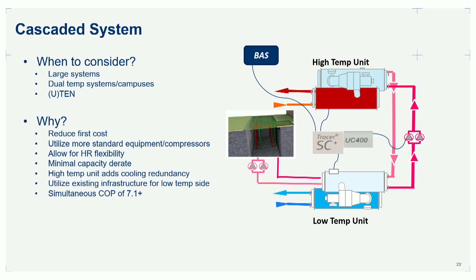Last but not least, I just have an example here to show this in practice, so you can believe me when I say that you can actually have a lower first cost by splitting this in half. This particular example happens to be air source, so please forgive me. I do realize this is a GEO conference, but the concepts transfer over regardless of what the source is. So in this case, we're using a cold ambient temperature of 0 degrees on the outside, and we've got a heating load of about 4.2 million BTUs. We're going to give it 0 coincident cooling load, so make it as hard as we can to source that heat. And we're going to try to do, in this case, 160 degree water.